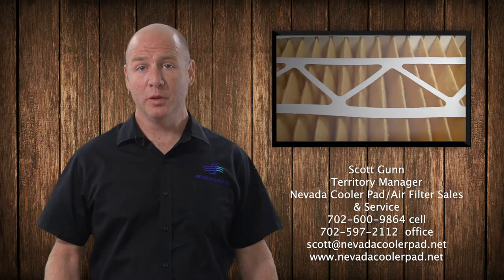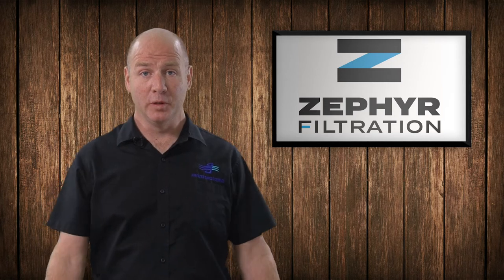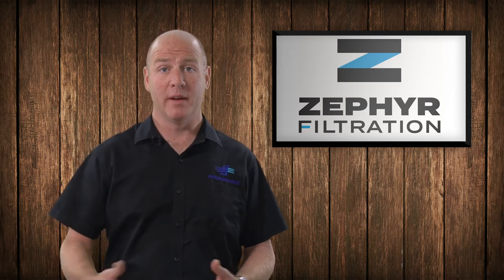The Zephyr is a three-inch filter that replaces most one-inch filter applications in all residential locations. With a lot of talk about viruses right now, we've offered a MERV 13 filter in our partnership with Blackbird to help mitigate some of those problems. A MERV 13 filter is designed to capture 46 percent of the airborne infectious particles that pass through it every time, so with several HVAC circulations it can help eliminate particles. The MERV 13 drastically reduces dust and provides three times the surface area of a one-inch filter, really allowing your system to breathe.